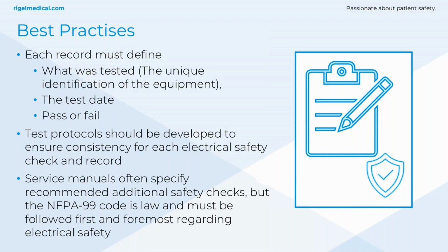So each record must define what was tested. So that's the unique identification of the equipment or the asset ID number, the date that it was tested, and whether it passed or failed. In most cases, people are still going to record the results. And within NFPA 99, there's only a couple of tests that you can perform. So test protocol should be developed to ensure consistency for each electrical safety check and record.